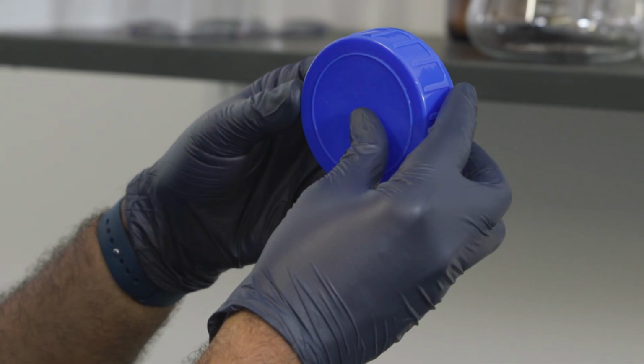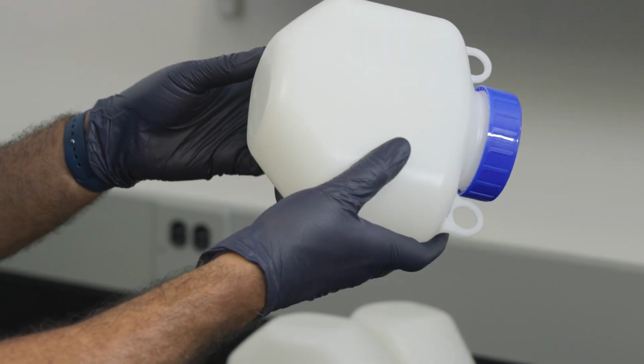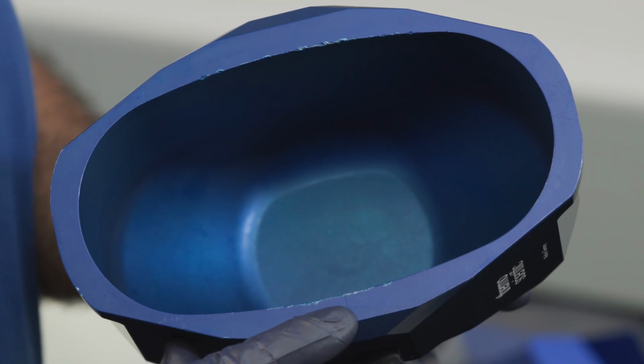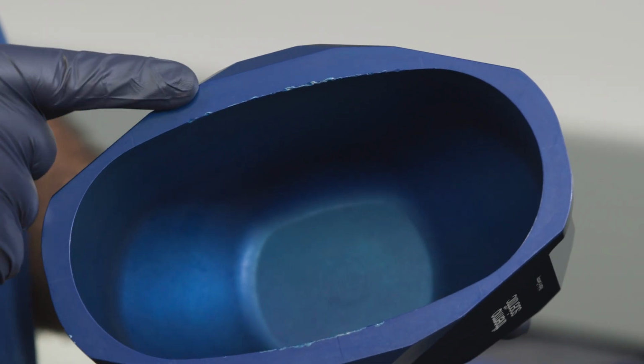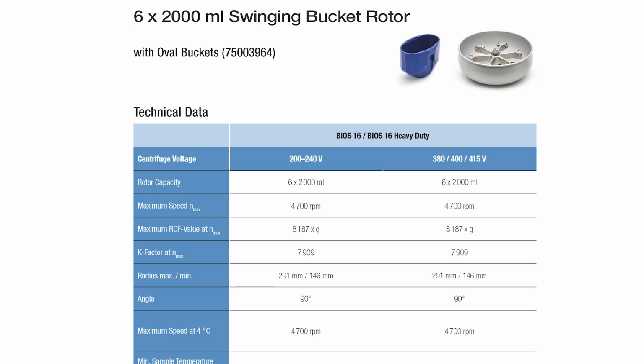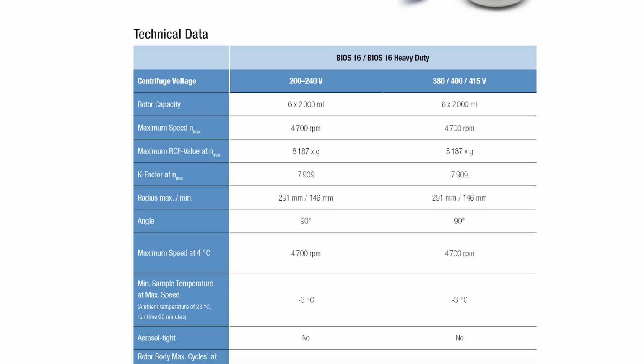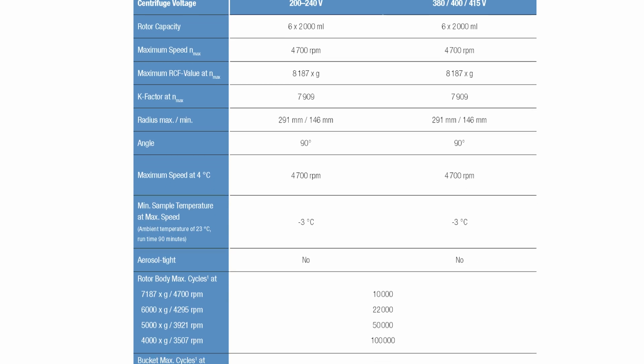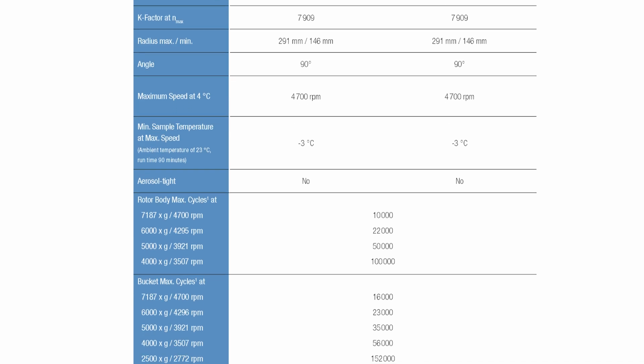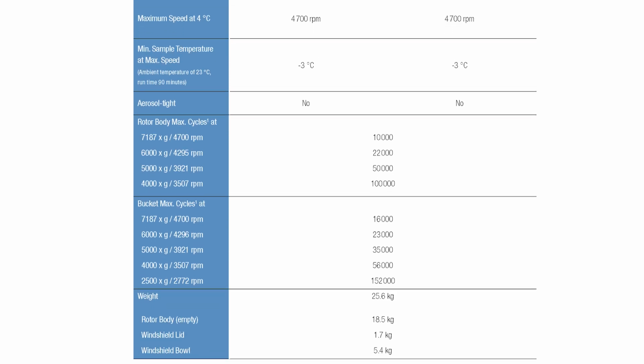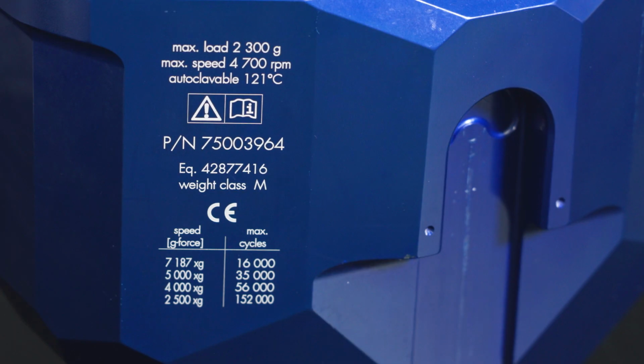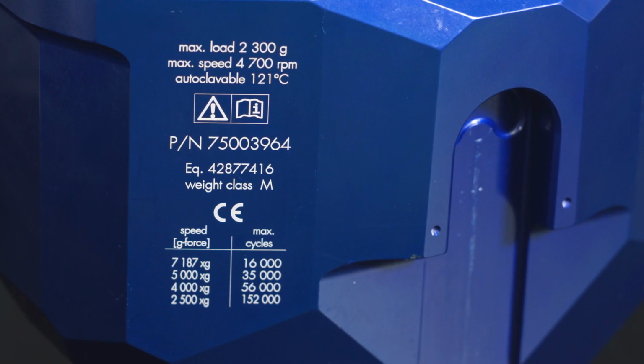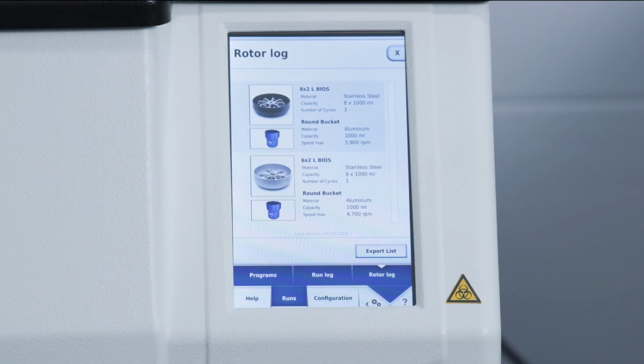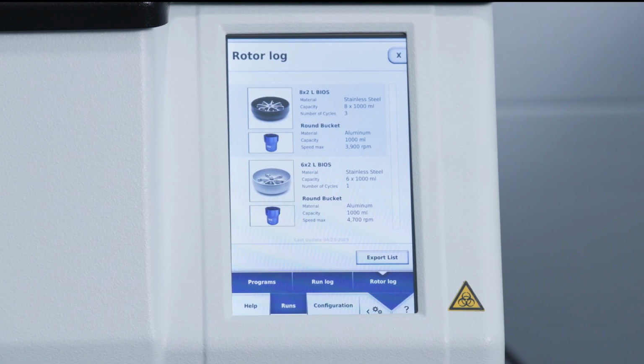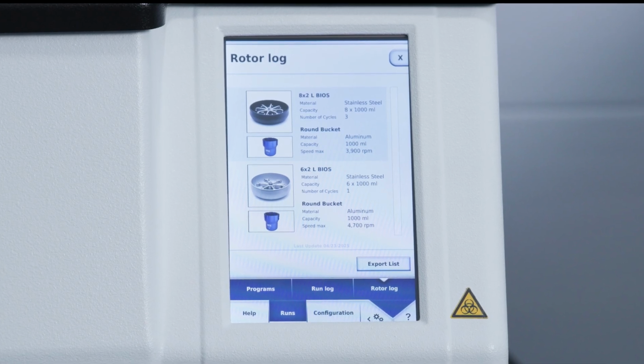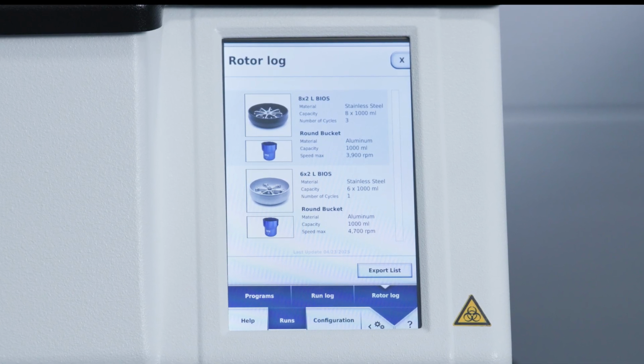Check for signs of plastic crazing, fading, bruising, or cracking too. Again, if items are damaged, they must be removed from service immediately. The service lifetime of a rotor and its buckets depends on the amount of physical load. Do not use rotors and buckets that exceed the maximum number of cycles. You can find this information for the rotor in the instruction manual. The maximum number of cycles for buckets is included on the buckets themselves. You can also check the number of cycles for a rotor type on the user interface of the centrifuge. The rotor log saves the information for rotors that have been used.